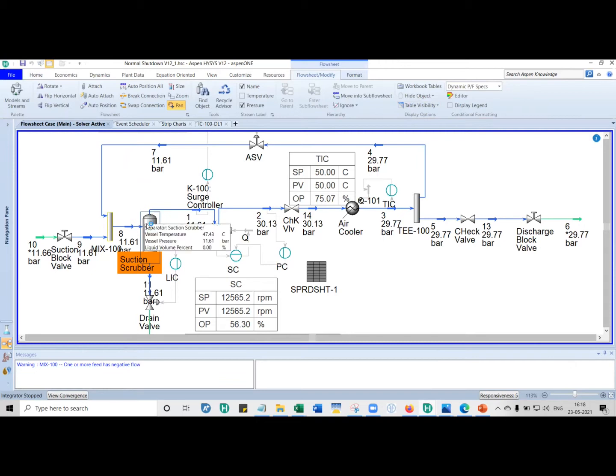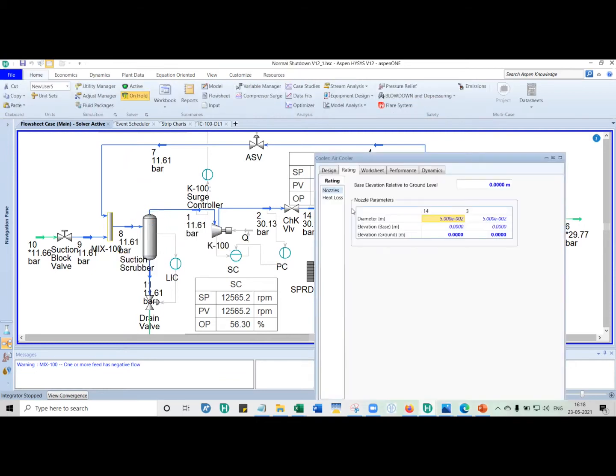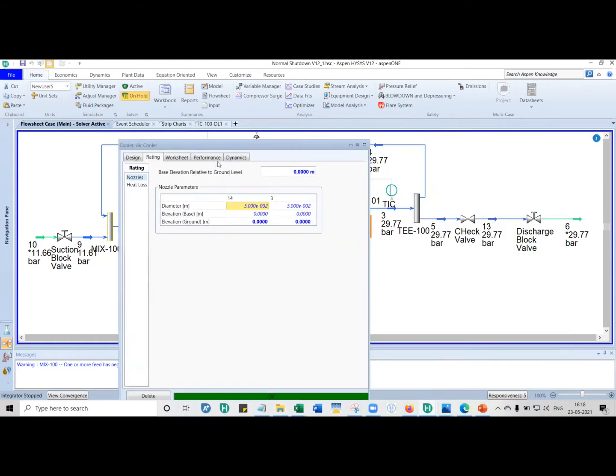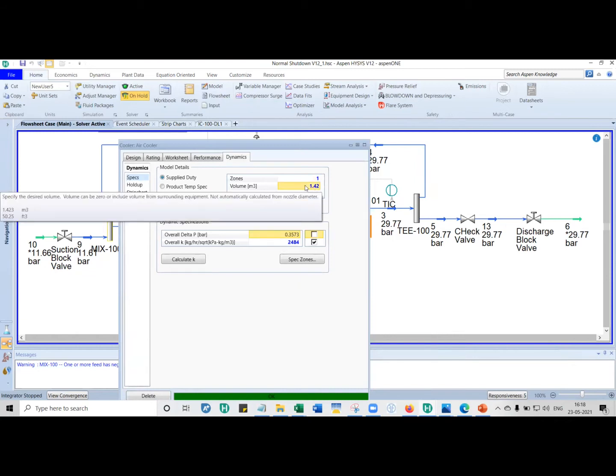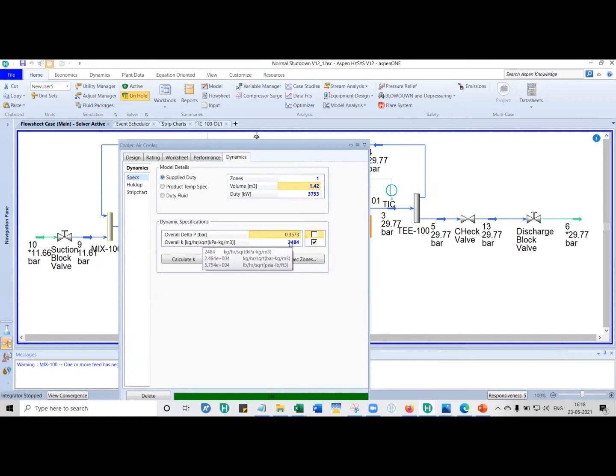For coolers, you not only give the cooler volume — after you size an air cooler you put the volume here, which is the volume of the tubes. That is pi/4 × d² × L, where d is the inner diameter of the tube and L is the length, multiplied by the number of tubes. You put that volume here. But you must also give what is called a K-value — the loss coefficient. It is basically the dynamic head, the kv²/2g value.